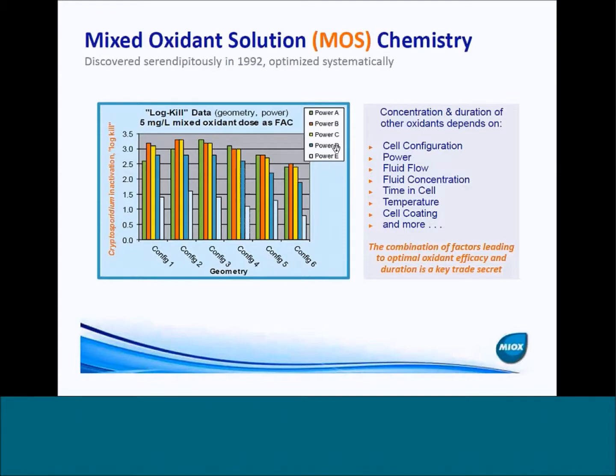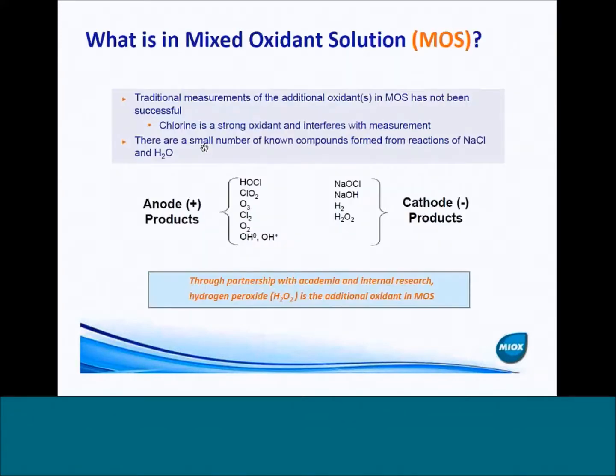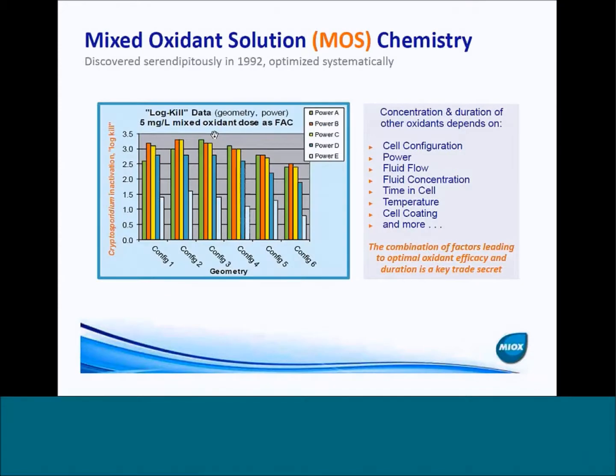At the same time, if you change the cell configuration — again, we're talking cell spacing, cell coating, et cetera — you can get almost all the way up to a three and a half log removal with cryptosporidium. This is at a little under a four-hour contact time at a five milligram per liter dose.